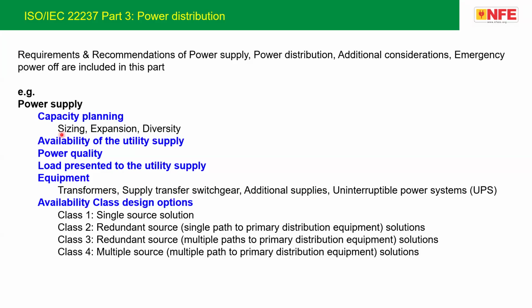It is also associated with the maximum load of the environmental control supply system and the predicted external ambient temperature and humidity. In addition to the IT load, we have to take care of the load required for security, lighting, building energy control system, and the battery discharge current. And because this campus and data center have a huge power requirement, there will definitely be losses also, which should be taken care of during sizing. From the operation point of view, we need the initial load, what the day one requirement will be, and how the growth of active power will come over time.